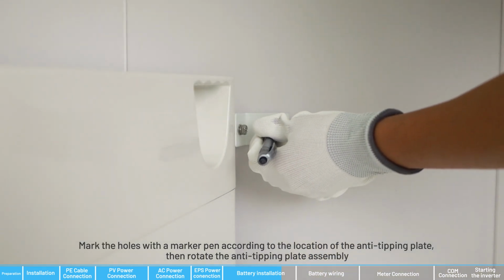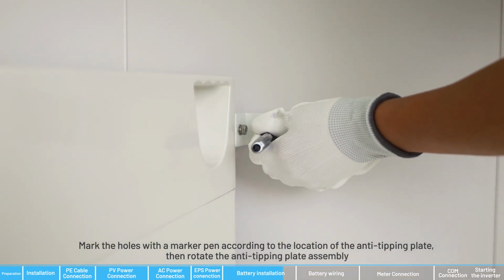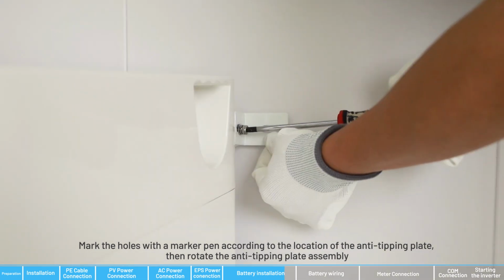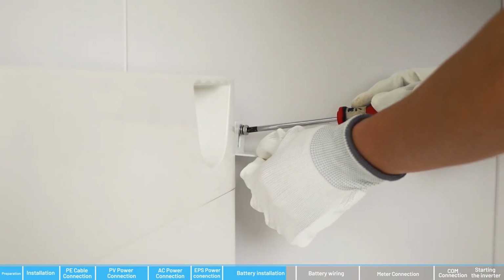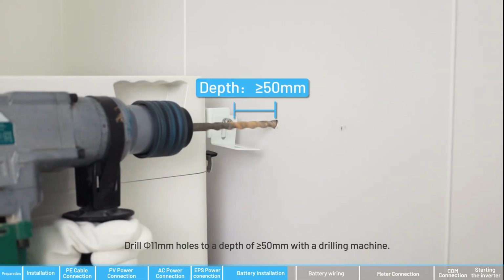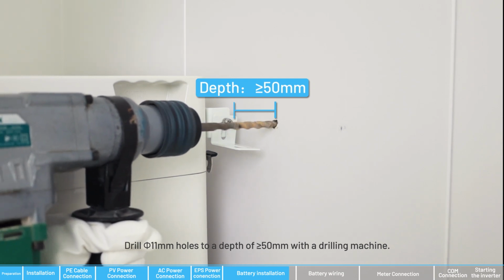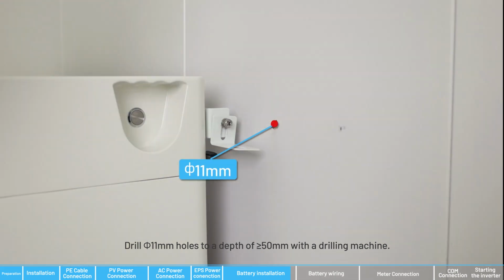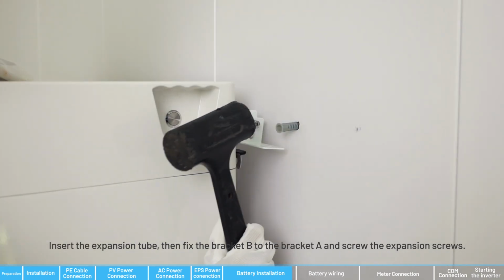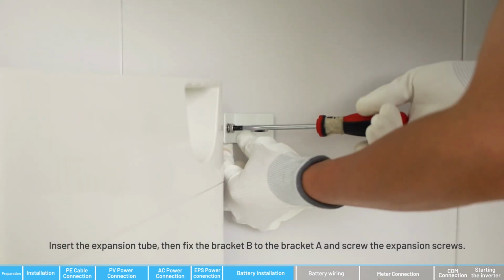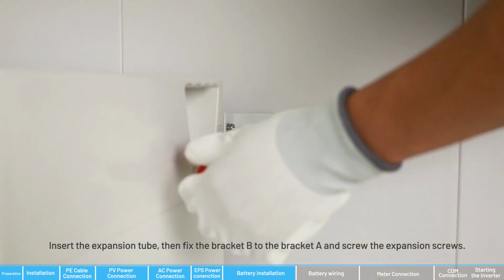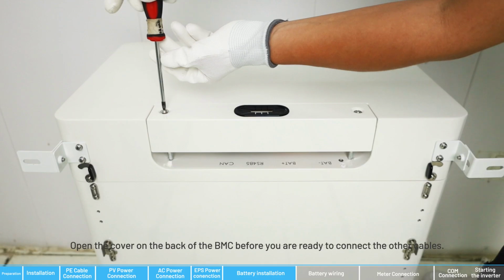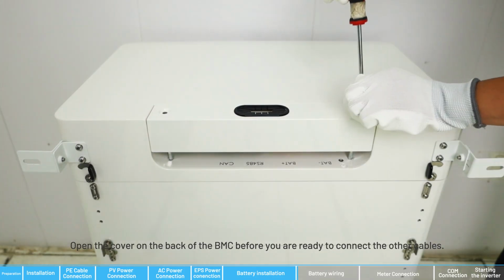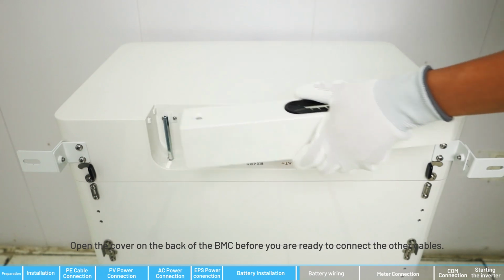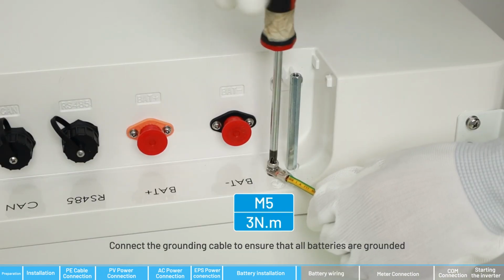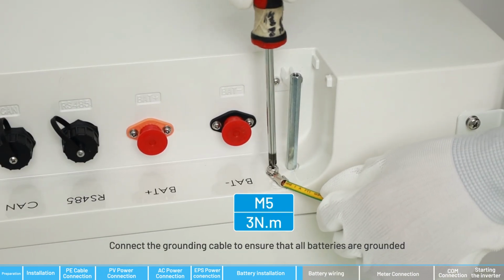Mark the holes with a marker pen according to the location of the anti-tipping plate, then rotate the anti-tipping plate assembly. Drill 11 mm holes to a depth of greater than or equal to 50 millimeters with a drilling machine. Insert the expansion tube, then fix the bracket B to the bracket A and screw the expansion screws. Open the cover on the back of the BMC before you are ready to connect the other cables. Connect the grounding cable to ensure that all batteries are grounded.